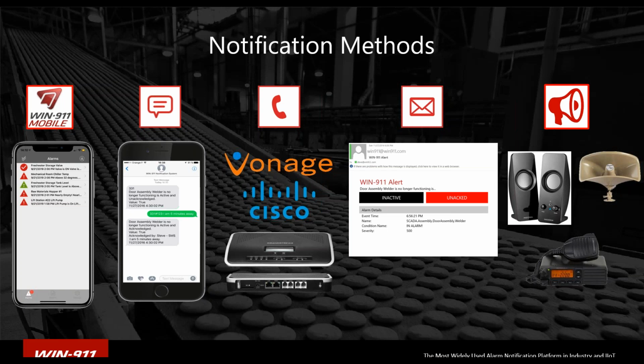And then finally, the announcer. This is an application that fills a few needs. One requirement is we've got a number of computers around the plant where we'd like to hear alarm annunciation over those speakers. This is a network program you can install on as many machines around the plant to hear those alarms. We've got a lot of nice features, building out the formats, converting strings that may not sound great over a text-to-speech engine, but are obviously defined in the SCADA since they have enough information visibly. So a lot of tools there.